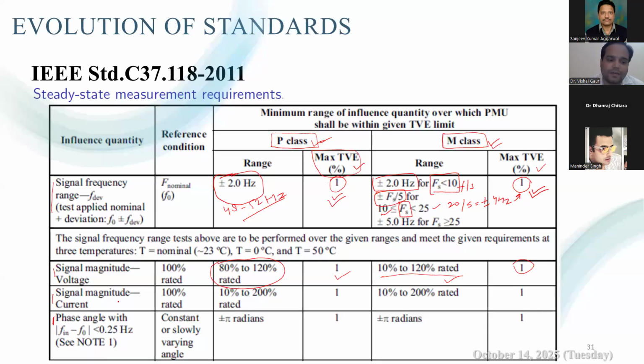Similarly, for current, they have defined that if the current signal magnitude varies from 10% to 200%, then also it should calculate the phasor with the accuracy, or with the maximum total vector error, of 1%. Similarly for M class. They have also shown the phase angle variation.